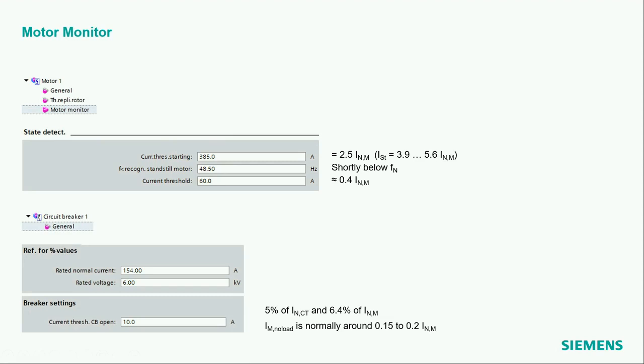And this is maybe 10% above the nominal current, not more, because of the K factor situation, class F and B, this discussion. So we get K factors around 1.1, 1.15, maybe, for motors. So I have enough space to that, 3.9 to 1.2. So I take something in the middle, 2.5. This should be fine, because here I'm far away from any overload situation of the motor as such.